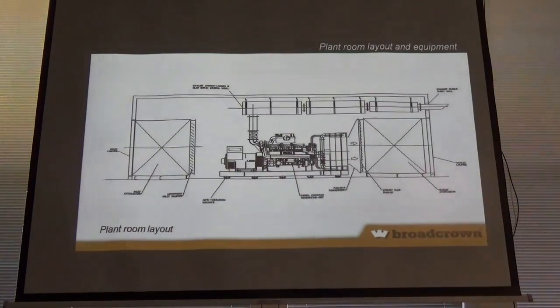Now you can put a discharge here, for instance, but if you've attenuated there, put your attenuator there and then turn it, you'll get noise breakout that will actually go into the ductwork. So if you attenuate it there, you'll have to line the ductwork. So by design, the best thing to do is basically put your attenuation at the leading point of the room itself. Then you can duct it, but you only need single skin ductwork and a turn-in section really to clear it. So again, by design, you can save a lot of cost and optimise the layouts, etc.